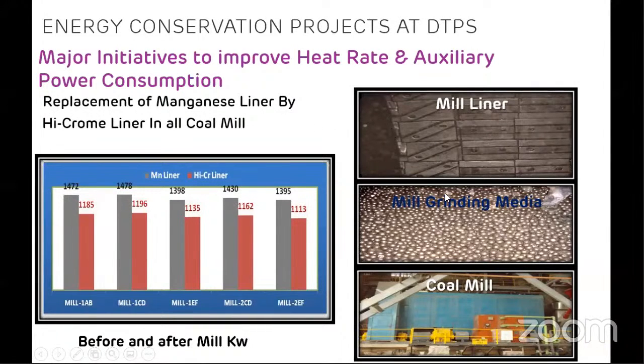This led to better grindability of the mill with lower power consumption. Like, we were getting a lower power consumption for the same amount of ground coal output from the mill. So here we have 6 coal mills, mill 1A, B, C, D, E, F, likewise. You can see that 1472 kilowatt was the consumption of mill 1AB before this modification. It reduced to 1185 kilowatt. So that much power was saved just by replacing the mill liners. Likewise, you can see in all mills, it changed from roughly 1470 or 1400 to 1100 kW.